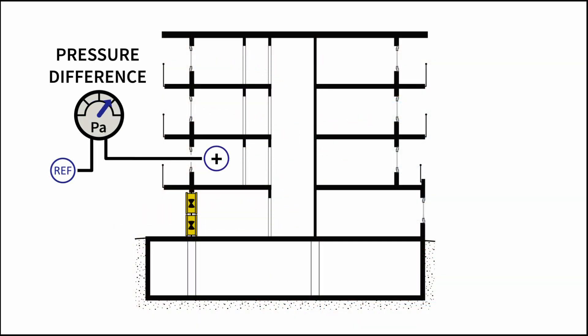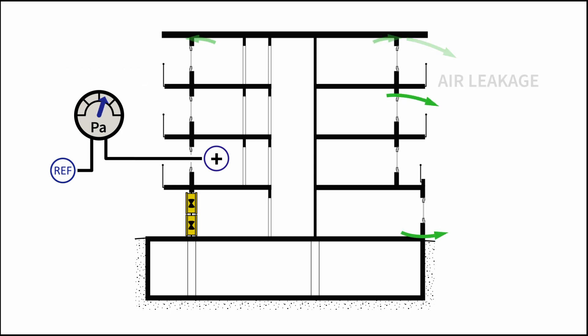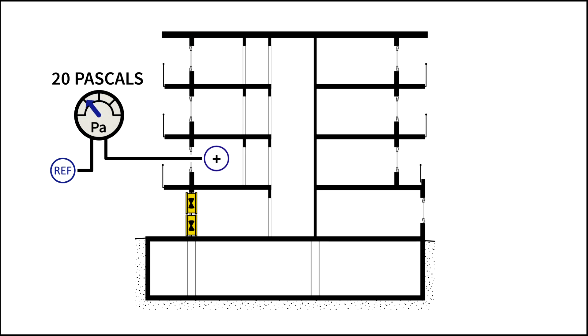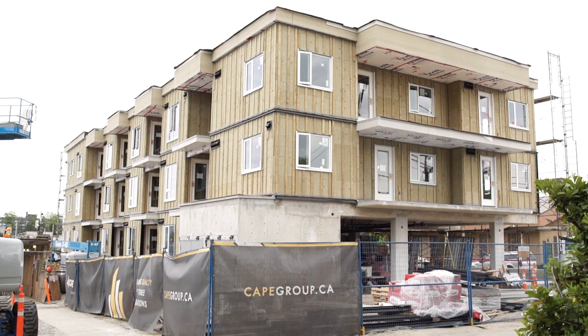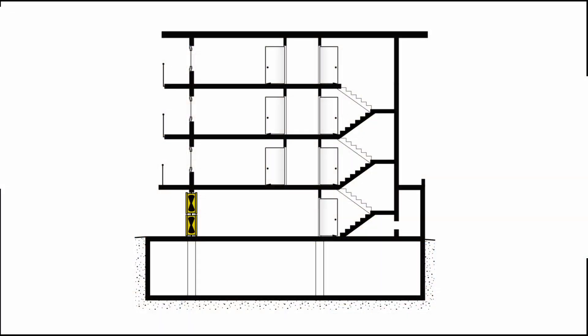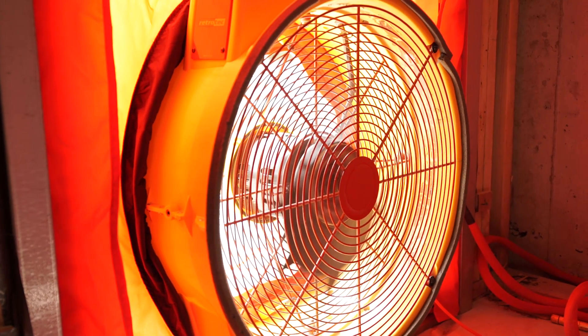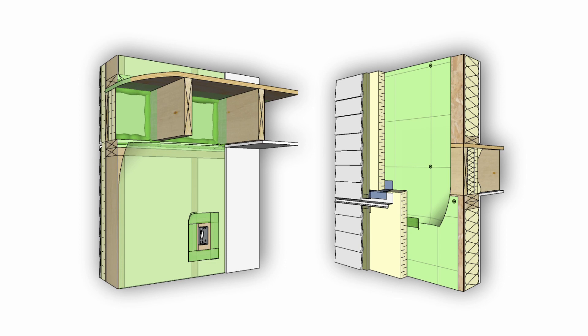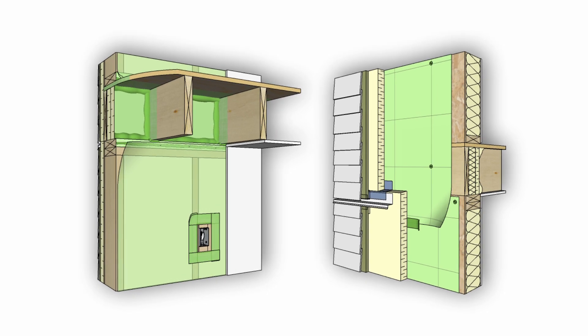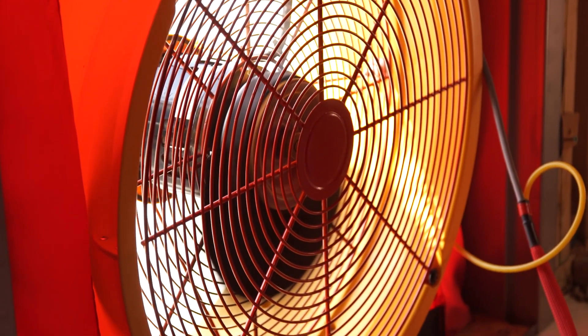Testing consists of pressurizing the building to a series of pressure differences and using the measurements to calculate and validate the building air tightness results. For large buildings, pressure differences of 20 to 100 Pascals are usually appropriate. To ensure even pressure distribution, pressure measurements are taken between interior areas at the highest ceiling elevation, lowest floor elevation, and on the windward and leeward sides. The blower fan is then flipped around and the same measurements are taken with the building depressurized. Note that some air barrier systems can be damaged during mid-construction testing if joints and seals are unsupported, so always ensure the test pressures will not strain the air barrier in its unsupported direction.